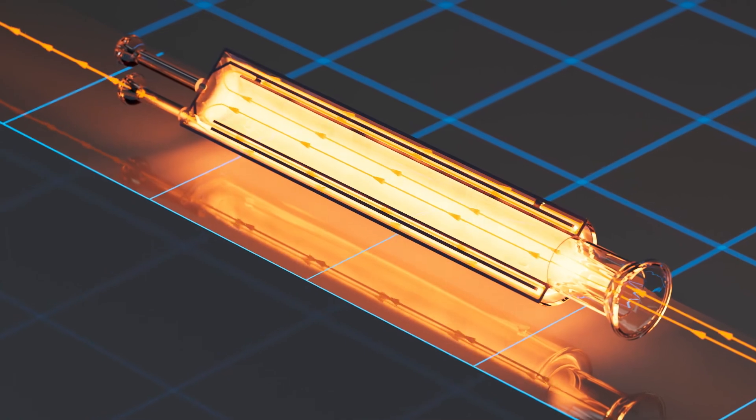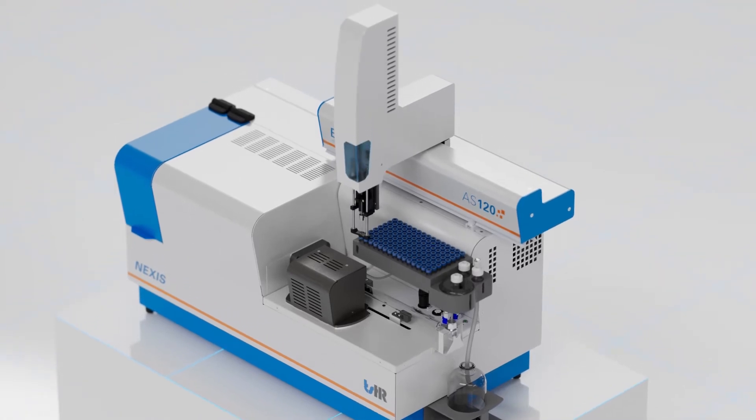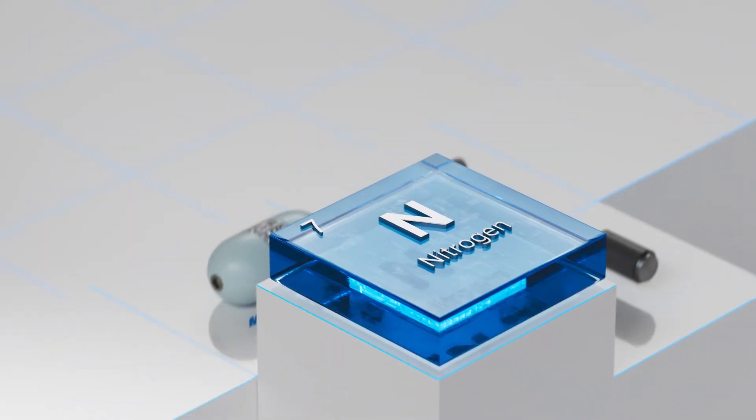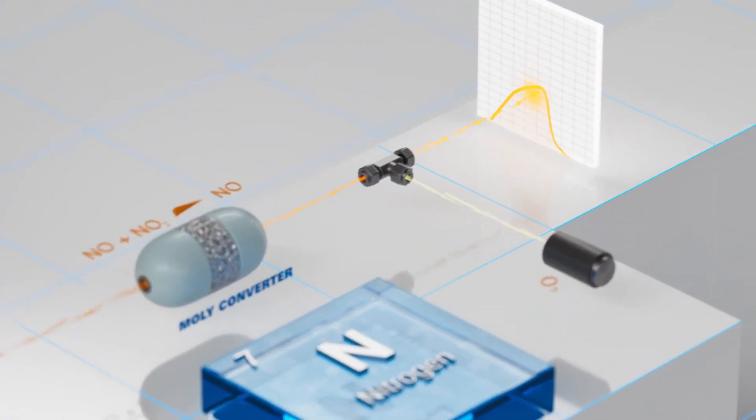This helps maintain compliance with even the most stringent reporting requirements. The NEXIS also uses an AC power supply that can better maintain consistent furnace temperatures and increase uptime. For total nitrogen analysis, the NEXIS features a moly converter which delivers unsurpassed low-level nitrogen detection.